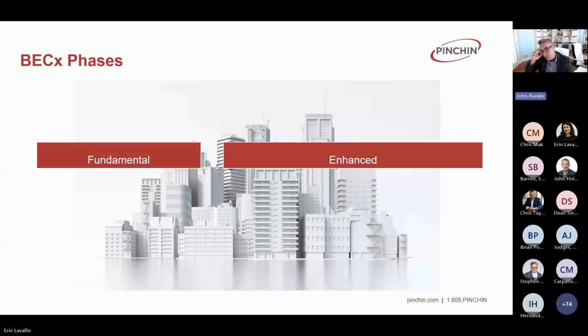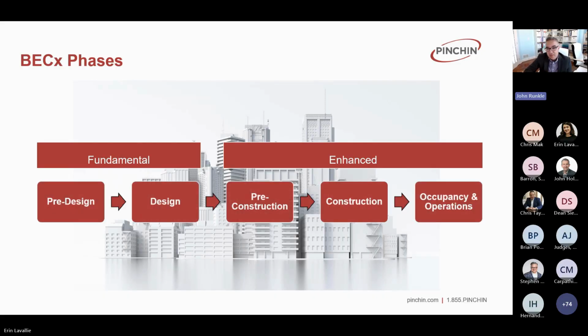And when you look at doing that, you can feel a little helpless sometimes. So one of the processes you can do is called commissioning, in this case commissioning of the building enclosure. You would also commission the HVAC systems and so forth. This commissioning can be done either as a retrofit or after the fact, but it starts with a review of the design, whether it's an existing building design or the design as it's being constructed, if it's new construction.